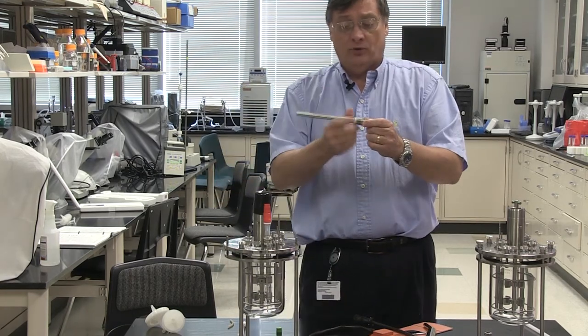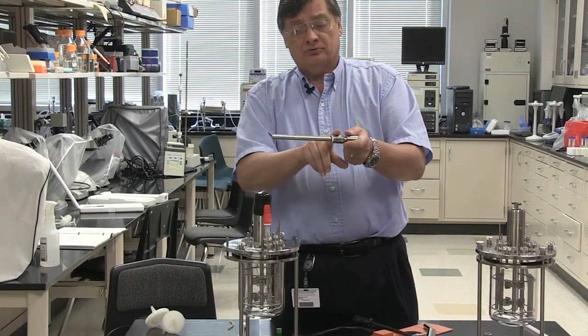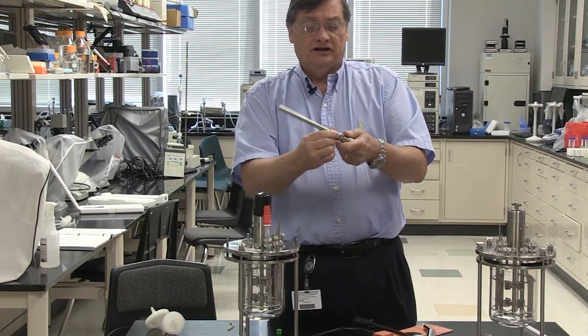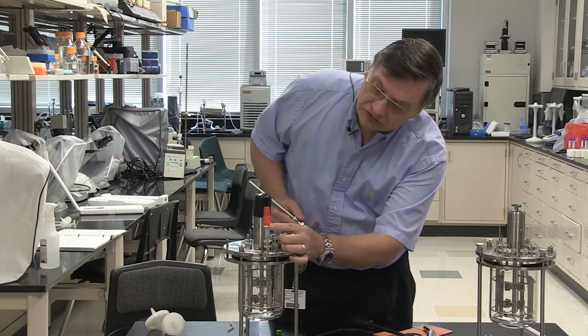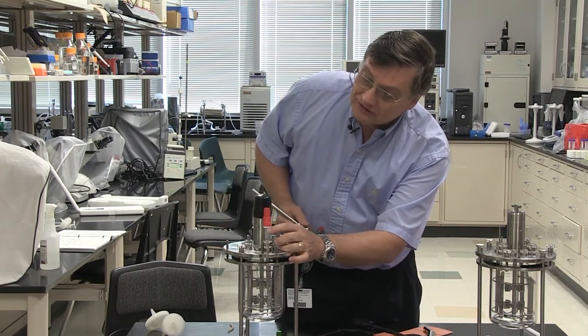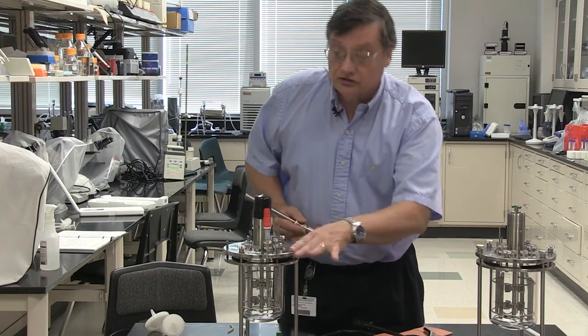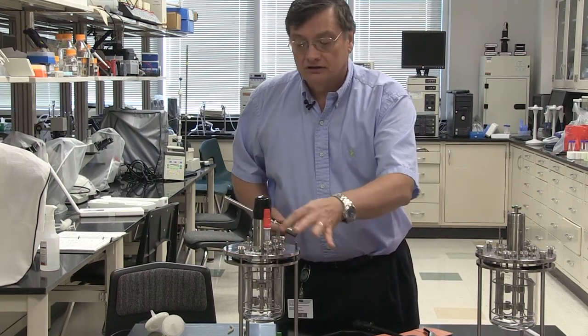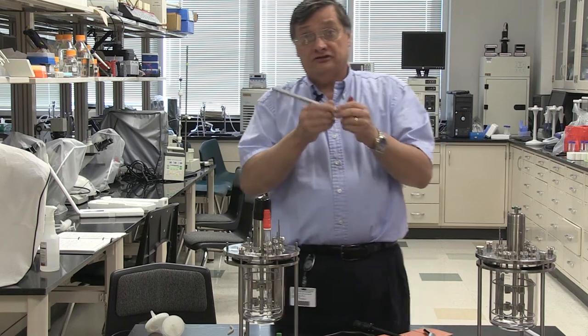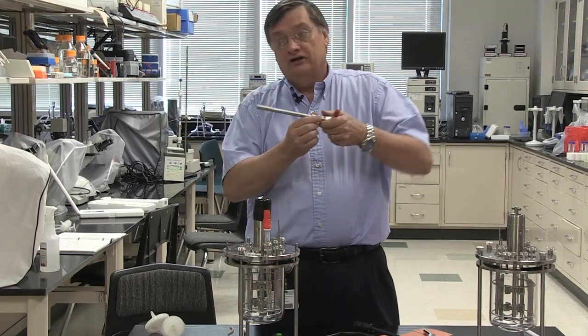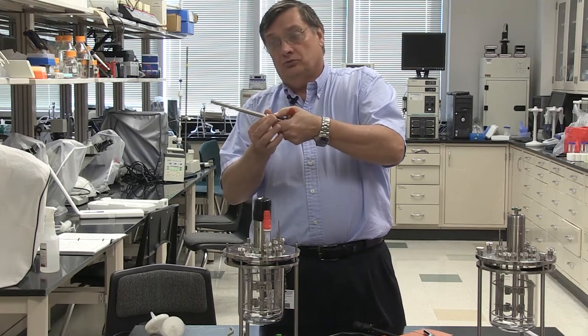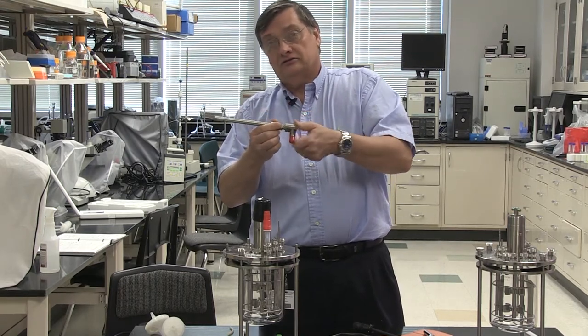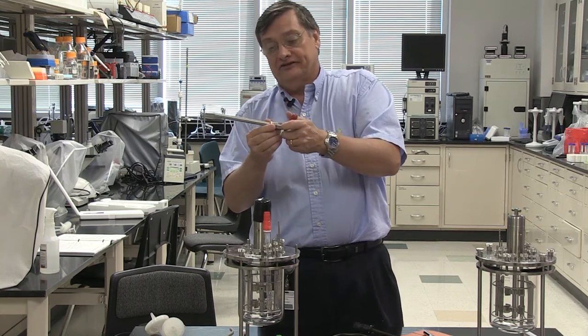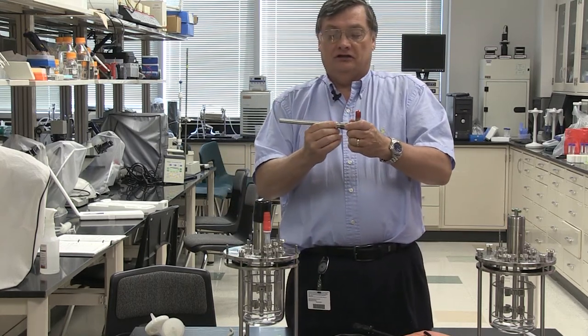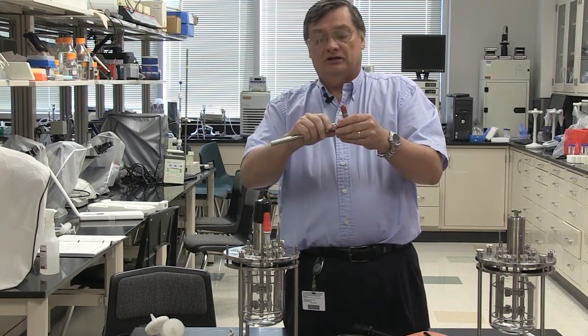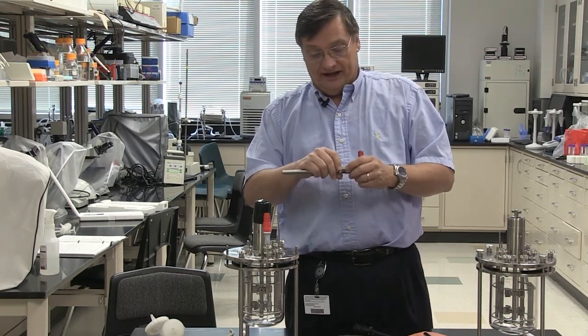But I'd like to point out there are some threaded fittings here and an O-ring, actually up on the top of the shaft. You'll notice there's a similar type of threads here on the pH electrode. Those aren't used with this vessel, right? These are used if this probe is used on a large stainless steel vessel, where this would go through the wall of the vessel and screw in and seat into the side of the vessel. So, not to be confused, they're just not for use with the vessels that we have.